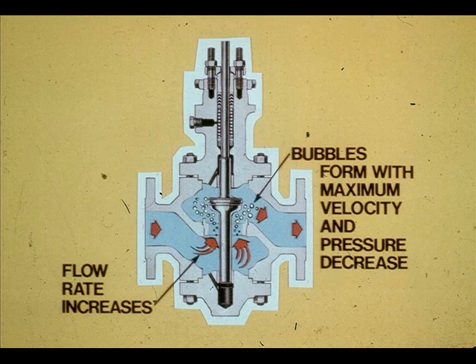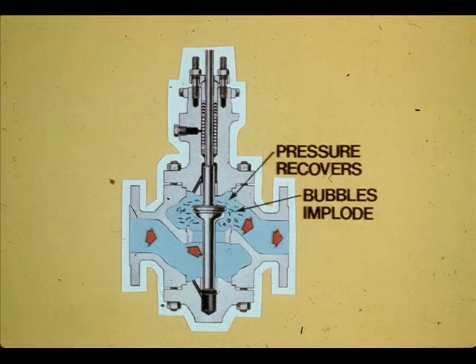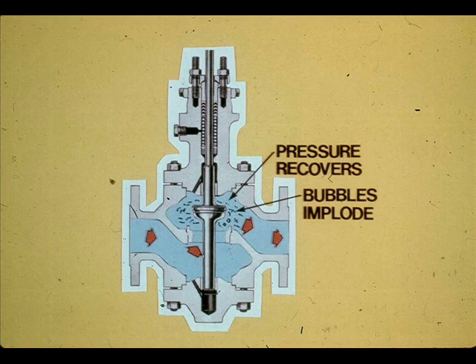Cavitation occurs in a control valve due to the pressure drop and pressure recovery inside the valve. The pressure drop causes the liquid to accelerate. The liquid pressure lowers and vaporization begins, thus forming vapor bubbles. The liquid then decelerates, the pressure builds back up, and the bubbles suddenly collapse, causing implosions.